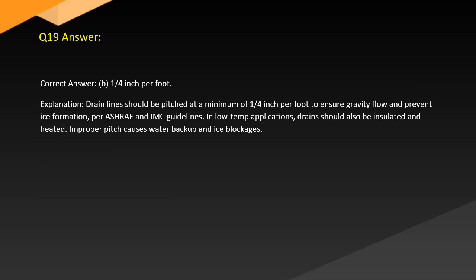Answer. Correct answer: B. 1/4 inch per foot. Explanation. Drain lines should be pitched at a minimum of 1/4 inch per foot to ensure gravity flow and prevent ice formation per ASHRAE and IMC guidelines. In low temp applications, drains should also be insulated and heated. Improper pitch causes water backup and ice blockages.